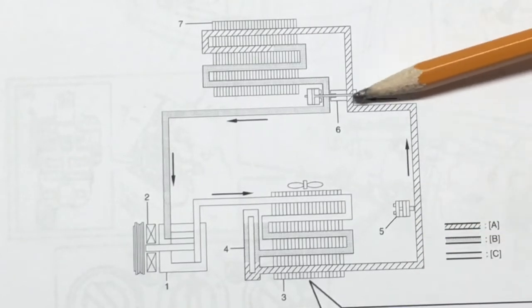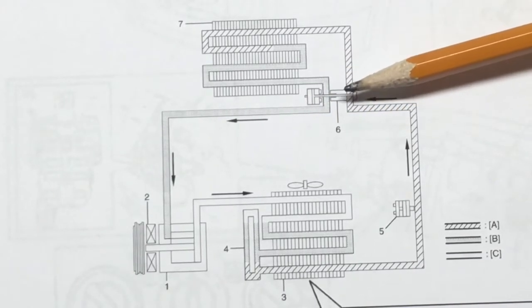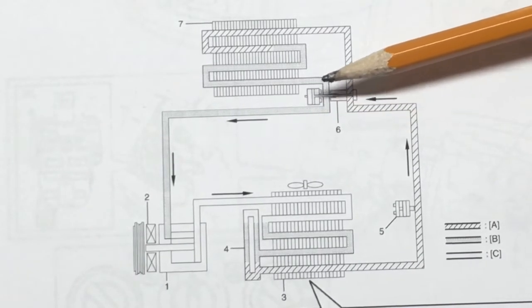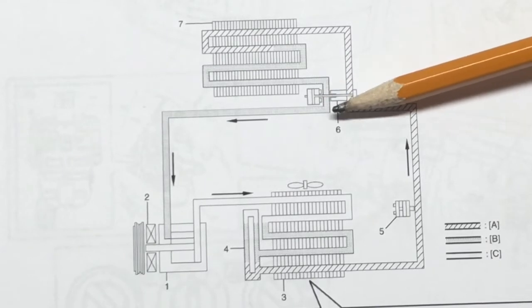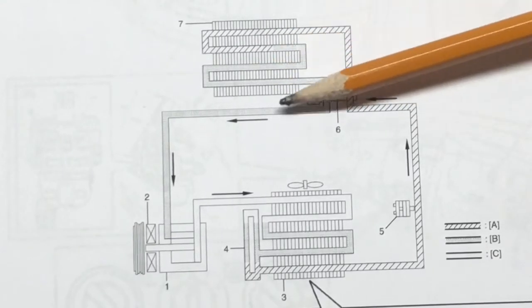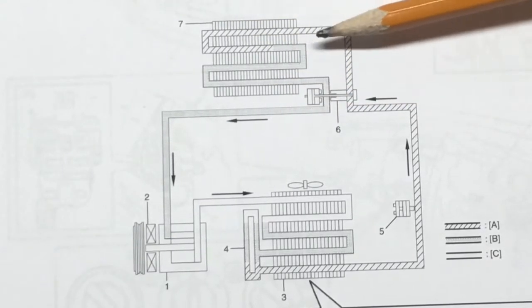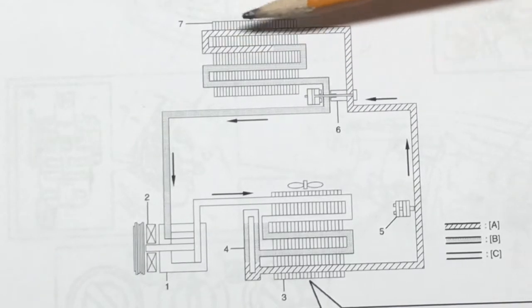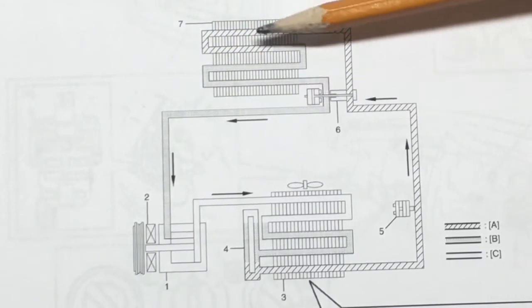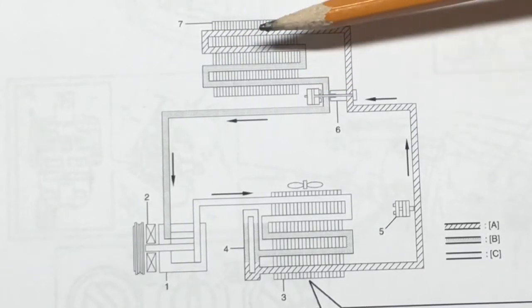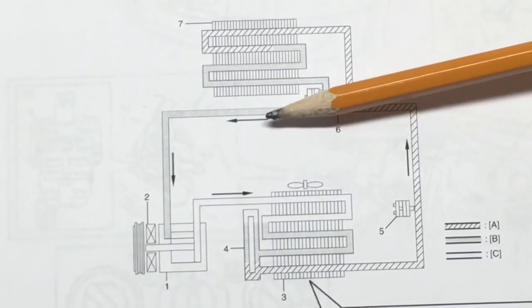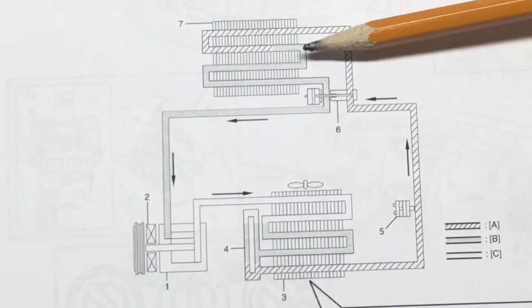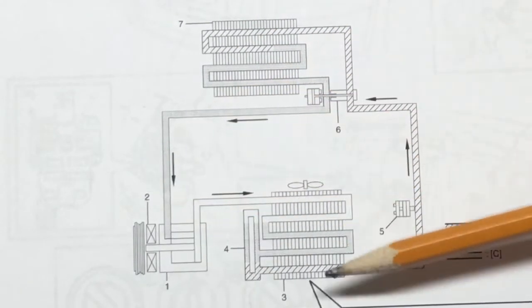So the high pressure liquid comes up to the thermostatic expansion valve. The thermostatic expansion valve basically releases that liquid into again an emulsion, part liquid, part vapor state, through the evaporator. And again, as the name implies, the evaporator will convert it from a liquid back to a gaseous state, absorbing the heat energy in the cabin in the process, and then the whole system repeats.